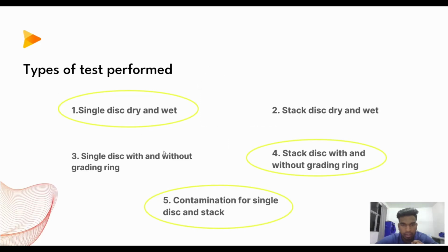We have performed 5 types of tests for the project. The first one is single disc dry and wet, stack disc dry and wet, single disc with and without grading ring, stack disc with and without grading ring. And the final one is contamination of single disc and stack.